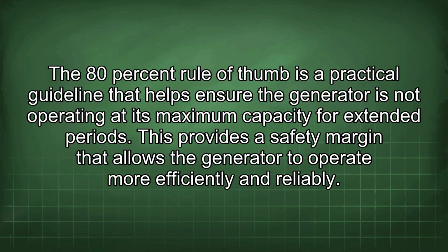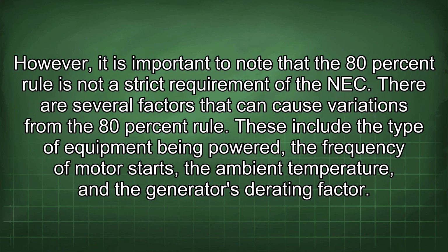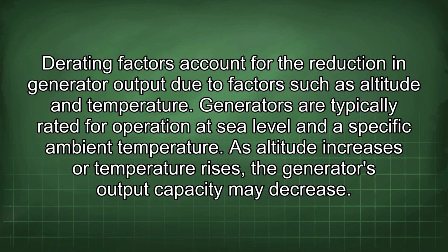The 80% rule of thumb is a practical guideline that helps ensure the generator is not operating at its maximum capacity for extended periods. This provides a safety margin that allows the generator to operate more efficiently and reliably. However, it is important to note that the 80% rule is not a strict requirement of the NEC. There are several factors that can cause variations from the 80% rule. These include the type of equipment being powered, the frequency of motor starts, the ambient temperature, and the generator's derating factor. Derating factors account for the reduction in generator output due to factors such as altitude and temperature. Generators are typically rated for operation at sea level and a specific ambient temperature. As altitude increases or temperature rises, the generator's output capacity may decrease.